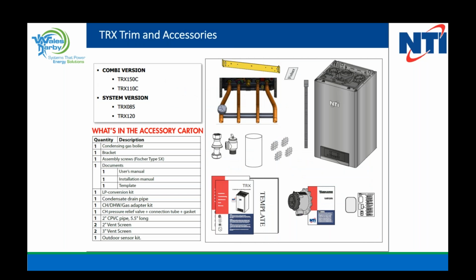All right, so here's the trim and accessories that come with the boiler. This is the parts and pieces that will come with the boiler. Obviously, you're going to get the boiler and a bracket. You'll get the manuals, user manual and installation manual, and a template so you can set it up properly on the wall. You'll get your condensate drain pipe, as you can see, a gas adapter kit, so if we're going from natural to propane, and a pressure relief valve. You're going to get 5.5 inches of 2-inch CPVC piping.